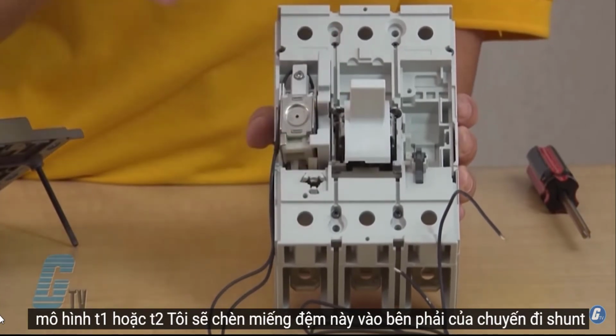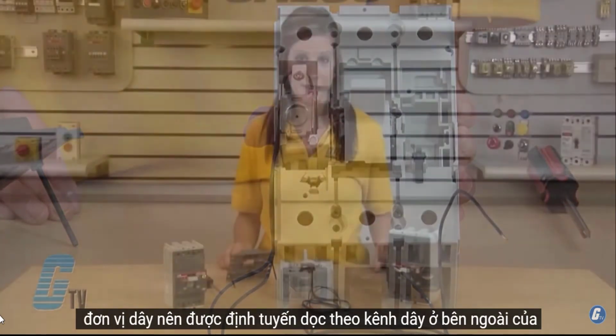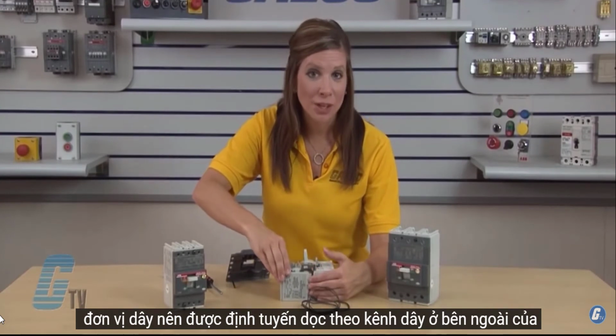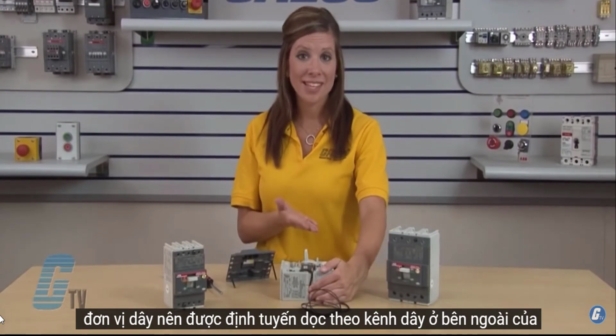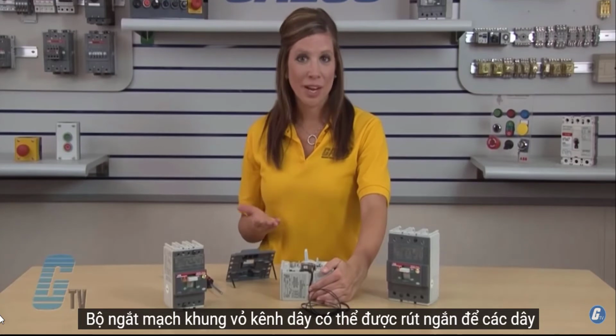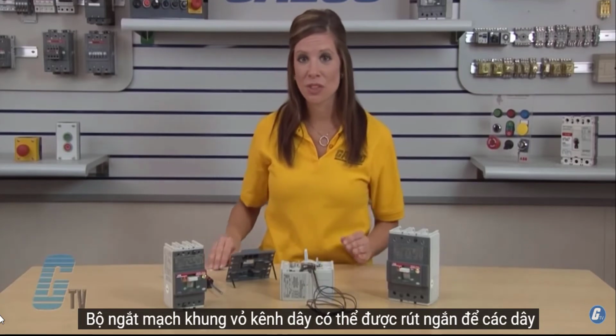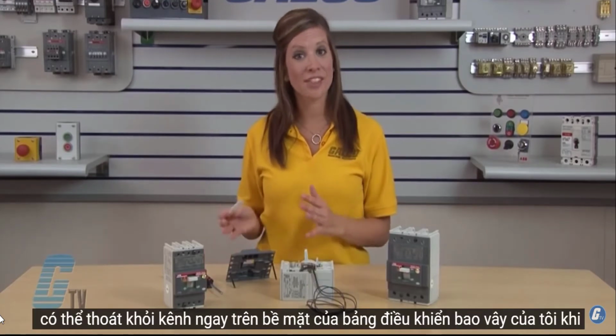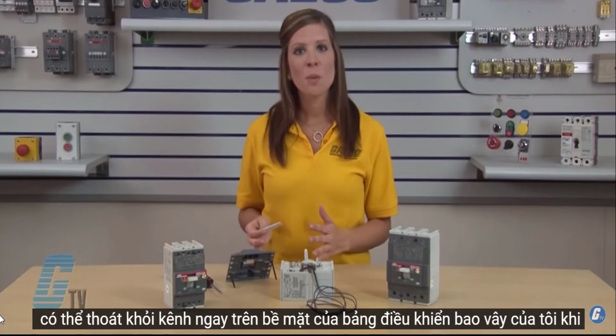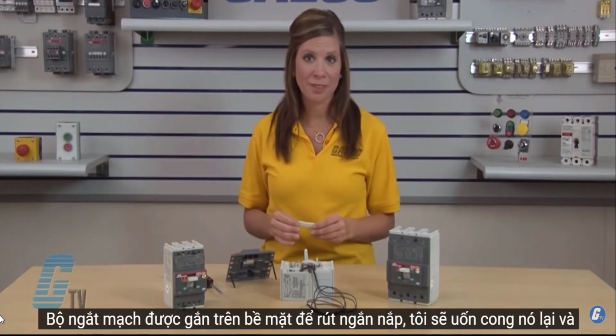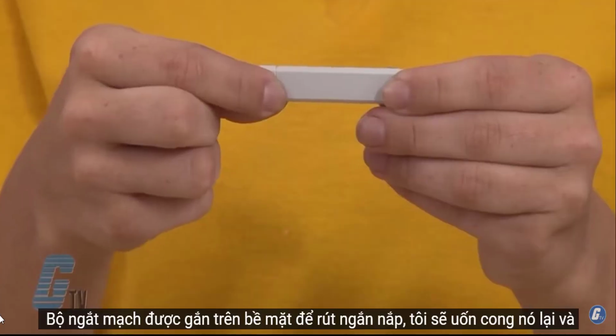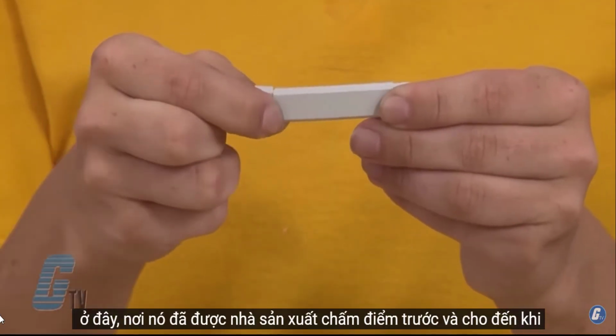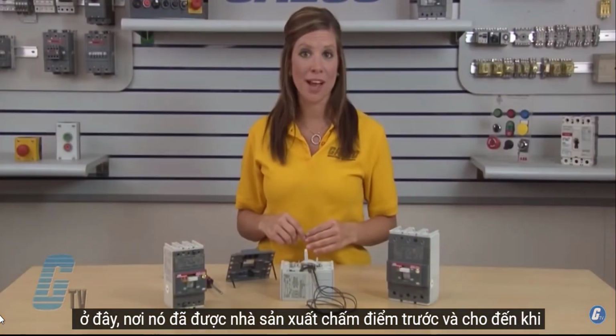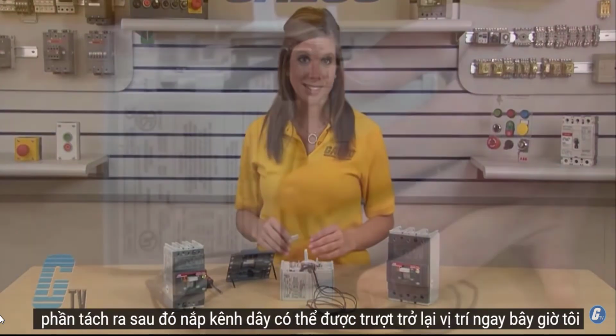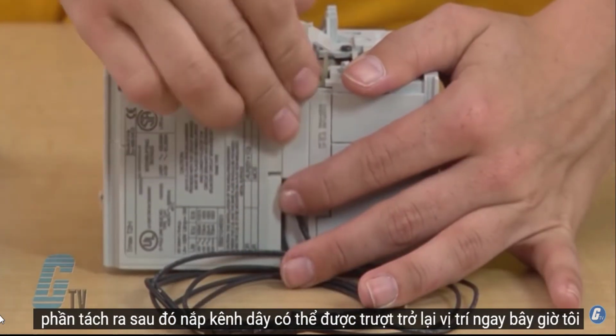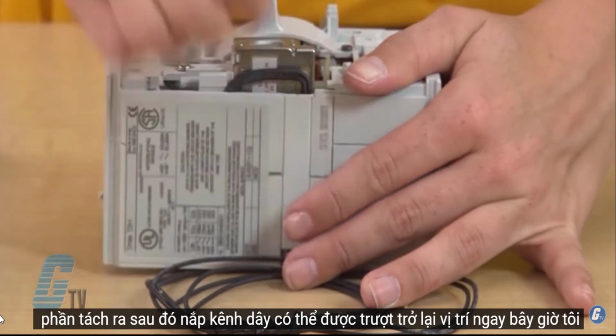I will insert this spacer to the right of the shunt trip unit. The wires should be routed along the wire channel on the outside of the circuit breaker frame. The wire channel cover can be shortened so that the wires can exit the channel right at the surface of my enclosure panel when the circuit breaker is surface mounted. To shorten the cover, I'll bend it back and forth here where it is pre-scored and notched by the manufacturer until the part separates. Then the wire channel cover can be slid back into place.